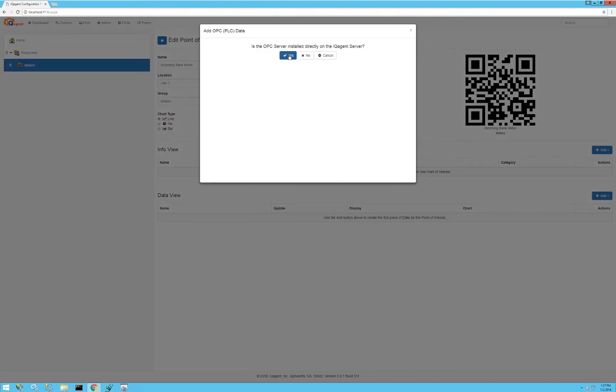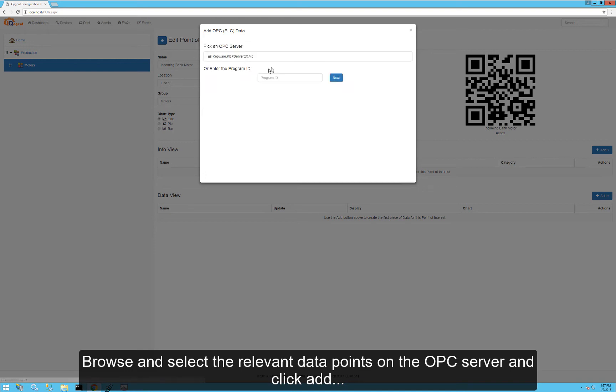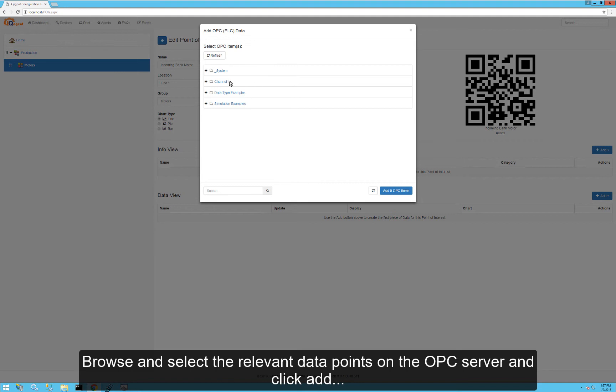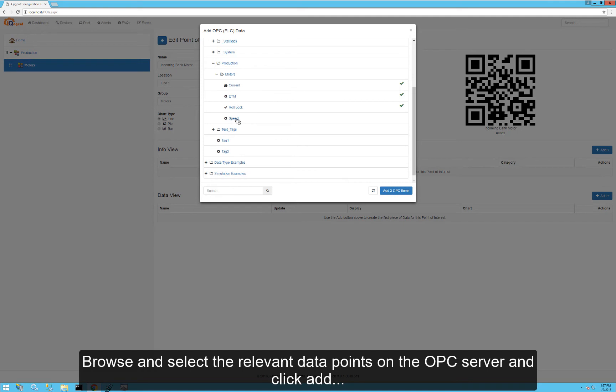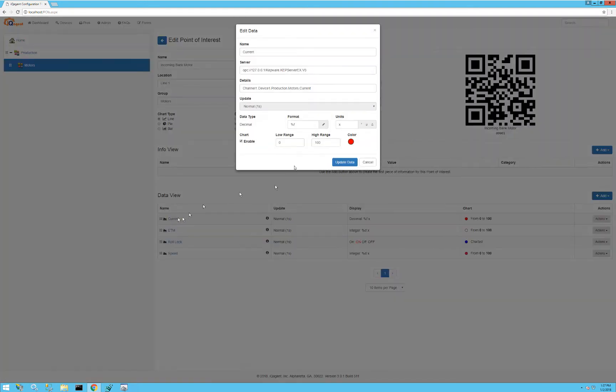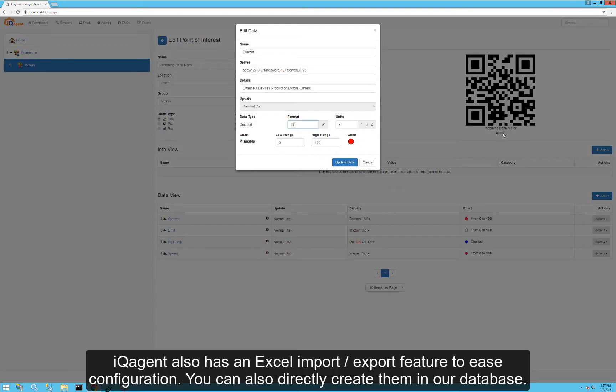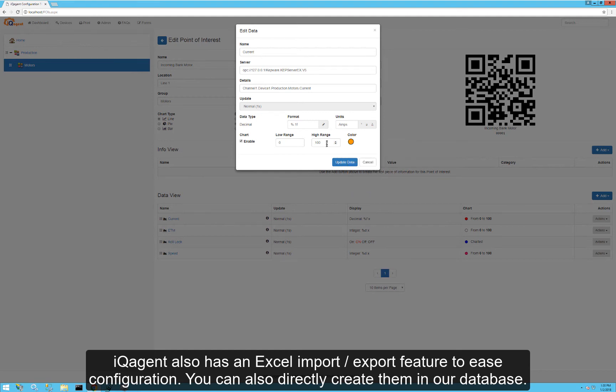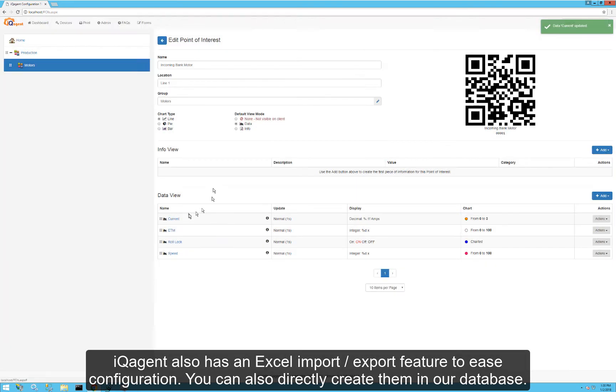Most SCADA systems and PLCs will support some type of OPC interface. Here we have Kepware, which is a well-known OPC server. We'll browse down to the tags related to our incoming bank motor. You can see they're different data types. I'll click add, and I can go in and edit these for format — so I can do 0.1F, which is a floating point. This is current, so my units are amps, and I can choose a color as well as a low and high range.